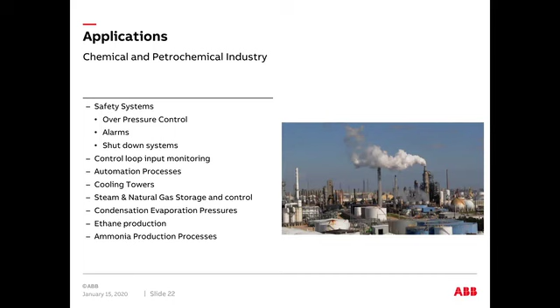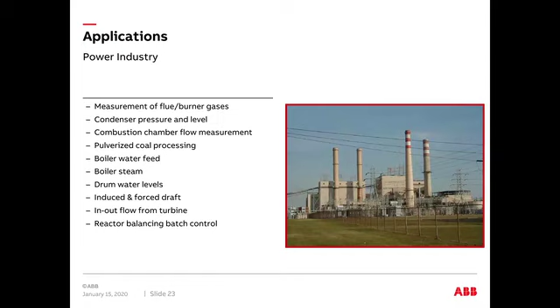You go to the power industry, you can have measurement of flue or burner gas, condensation pressure level, combustion chamber. If there's pulverized coal processing, if there's boilers, you're going to have water feed and steam pressures coming from those. The draft that you may get, whether it's induced or forced, you've got in and out flow from a turbine. You move on to something like this where you're measuring the gas, so you need high performance measurement to control the fuel and the combustion. So with the ABB solution, we have very low pressure ranges that you can use to control what's going into there. Differential pressure you can use to adjust the flow or to cut off the flow.